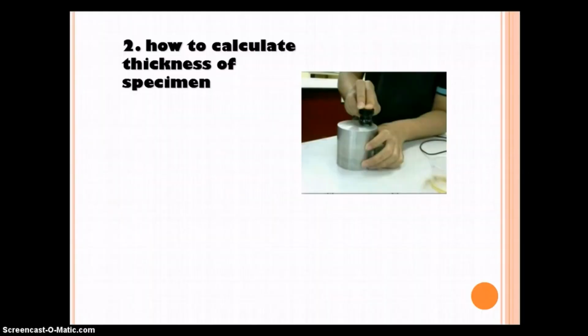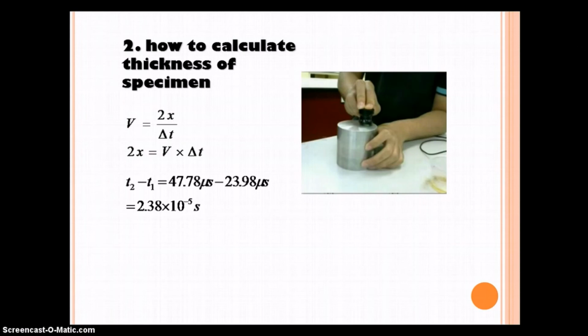The second calculation is our main objective, that is to find the thickness measurement of the specimen. Using the same formula as before, V equals 2x over delta T, we rearrange it to 2x equals V times delta T. First of all, we find the delta T that we obtain from the PicoScope. Then we apply it to the formula. Since both are the same material as in the first calculation, we take the velocity 6379.85 meters per second, multiply it by delta T, and divide it by 2. The result is 0.0759 meters.